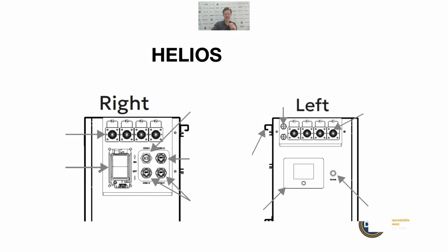So you do need, to meet the best practice guide, a 2-pole breaker after the battery. It doesn't need to be 200 amps. If you're using a single battery, you'd probably use a 200 amp breaker. Obviously anything larger than that is pointless, because the built-in breaker is 200 amps.